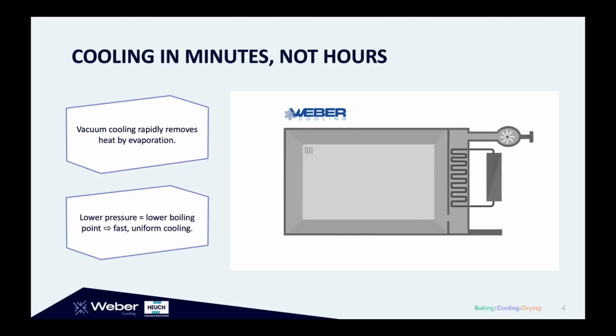Now, the great thing about vacuum cooling is that you cool the product from the inside out. So it's very different from a blast chiller or conventional cooling method. Here, you don't blow air trying to cool the product from the outside to the inside, which does not give you any guarantee that the core of the product is really cold. But here you have the guarantee that because you are cooling from the inside out, all the product will be evenly cooled. And it doesn't matter if your product or your tray is at the top, in the middle or below, the pressure is the same. So the cooling is the same, it's uniform. And that's one of the main advantages of vacuum cooling.